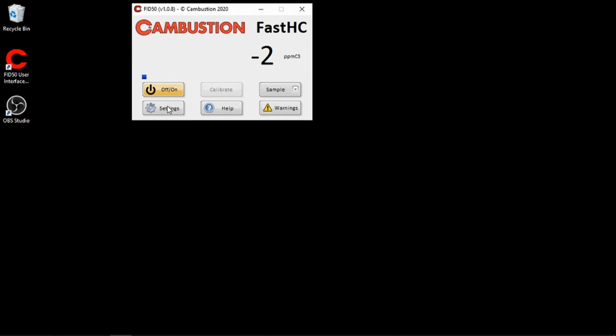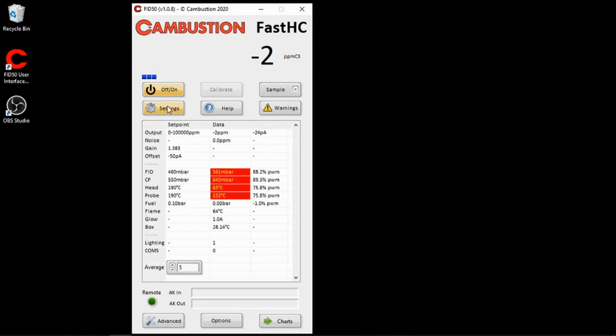If I open this settings window, you can see all of the parameters which are being controlled inside the analyzer, and we can see the glow plug current, for example. We can see our flame is lit and that temperature is rising. We can see the sample probe temperature has reached our 190 degrees and is coming into control. So there are lots of things in here which are stabilizing. We have to leave this for about 5-10 minutes until everything is established and stable.